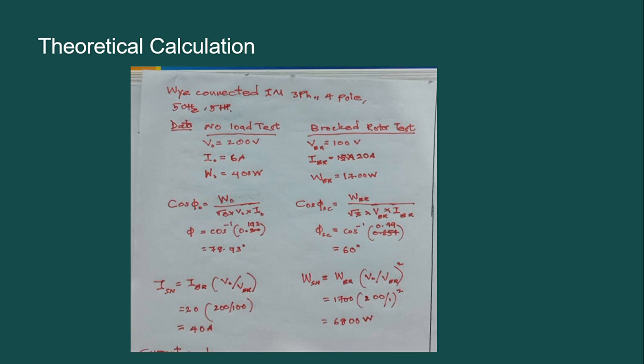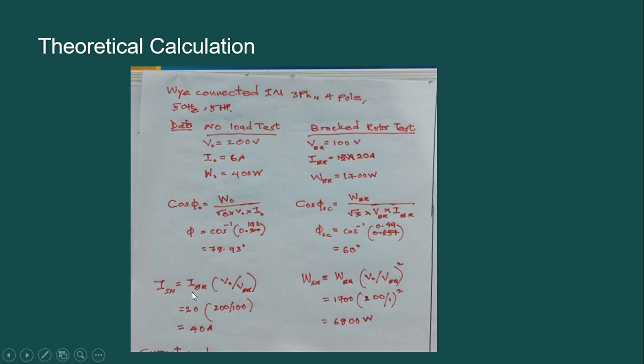To convert that, we have a formula: ISN equals blocked rotor current multiplied by (V naught over V_BR). After putting the given data in the equation, we get ISN equal to 40 ampere and WSN equal to 6800 watt.